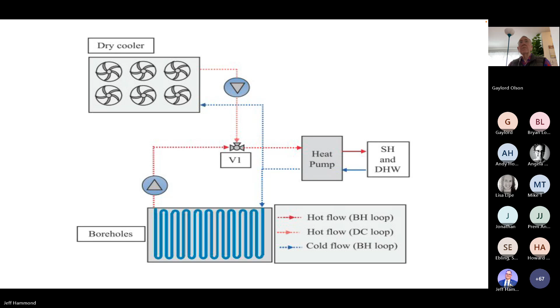Moving along to the next one: this is also a dry cooler in combination with a ground loop, but this is level 2, not level 1. It gives preconditioning capability, or regeneration in European parlance. You notice also there's the valve, valve V1, which can either allow the water to go through the dry cooler and then in series with the ground loop, or it can totally bypass the dry cooler and use the ground loop by itself.